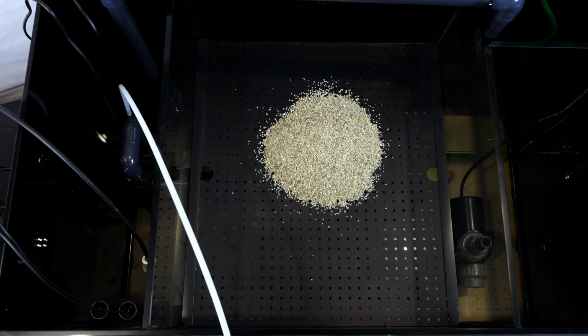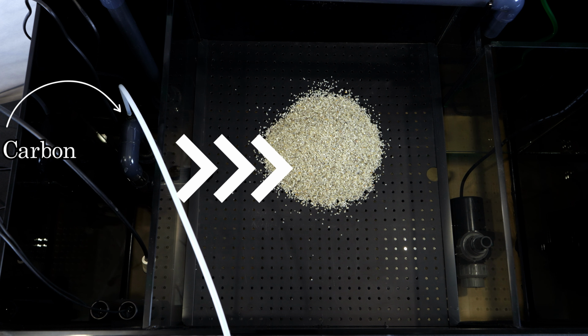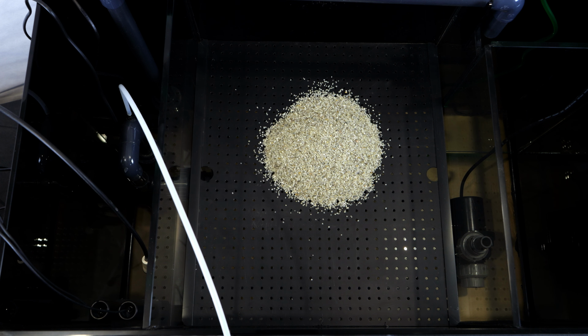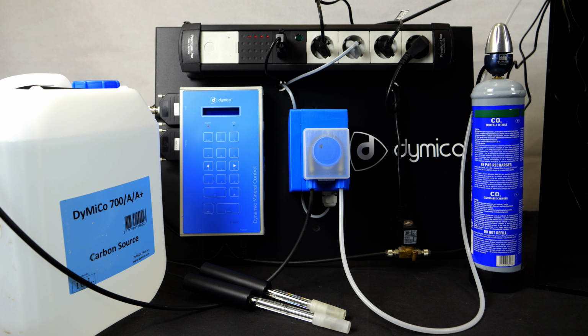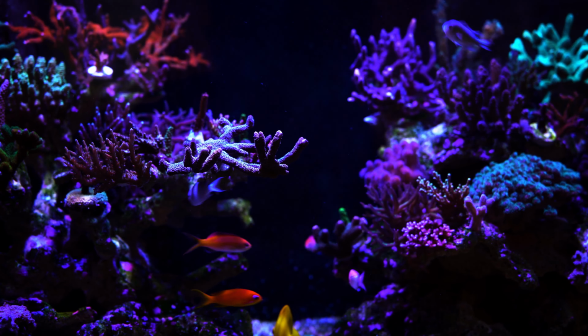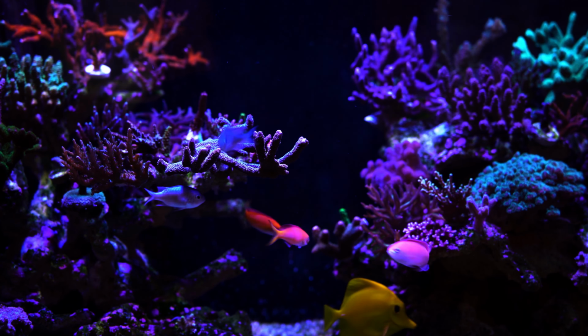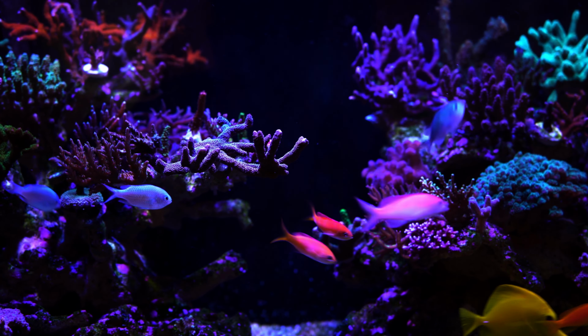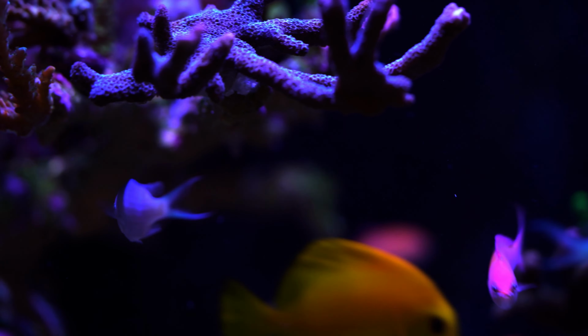After probably 30 seconds, it will stop. Then the carbon dosing pump will run and the process pump. Then if pH is higher than the desired value, the solenoid valve will open to release CO2 into the DyMiCo system. Don't be upset if the process, return and carbon dosing pumps are running for only a short period of time. DyMiCo is processing a fraction of the water volume every hour. The maximum running time for the process pump is 16 minutes per hour. The average is 4 minutes per hour.